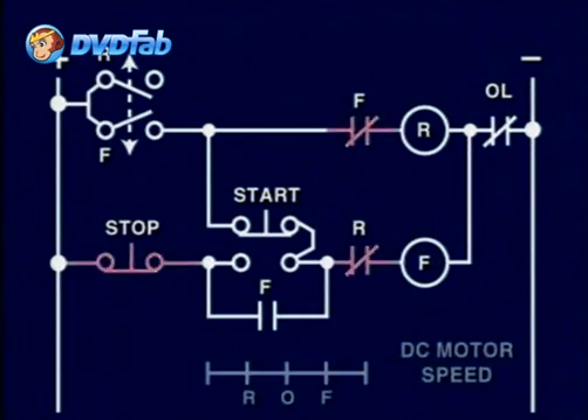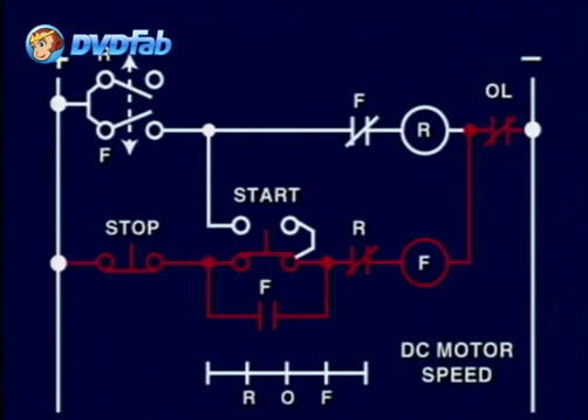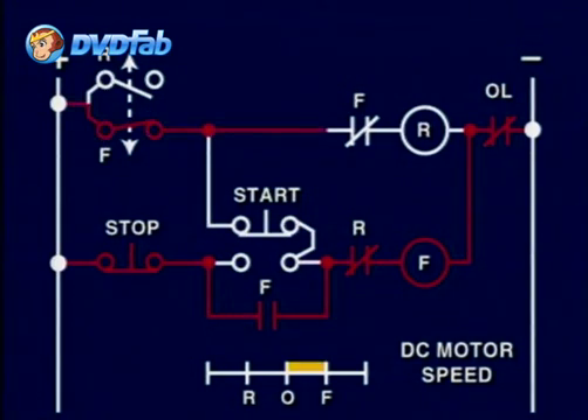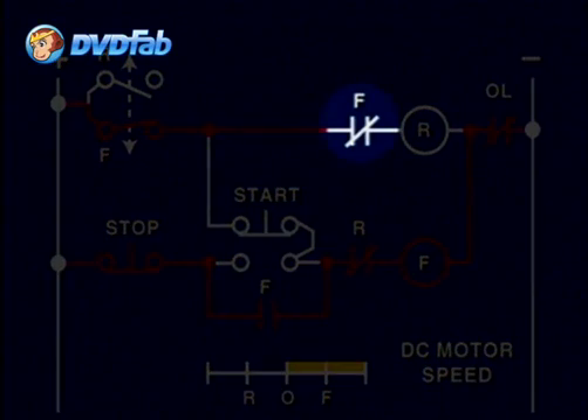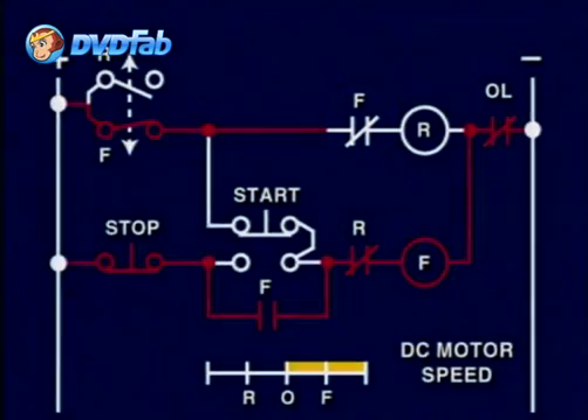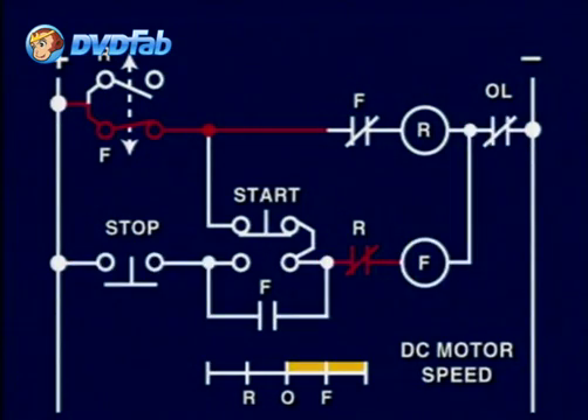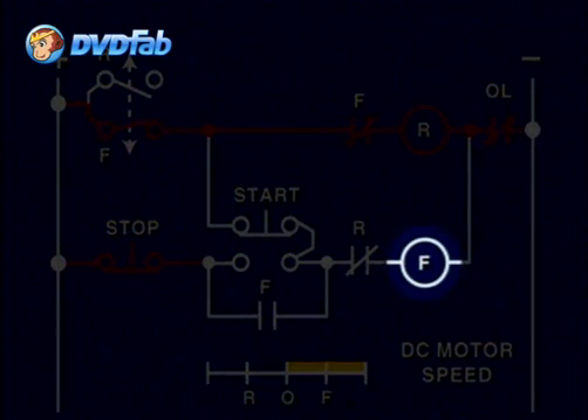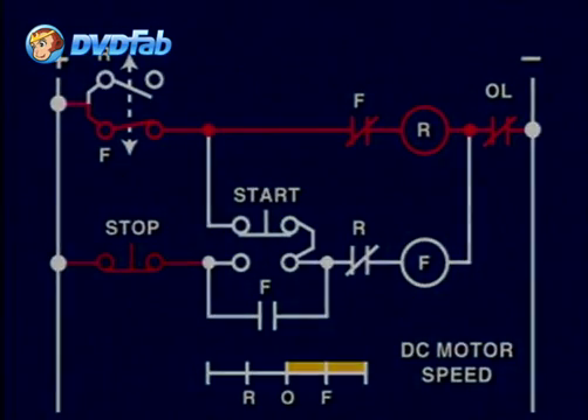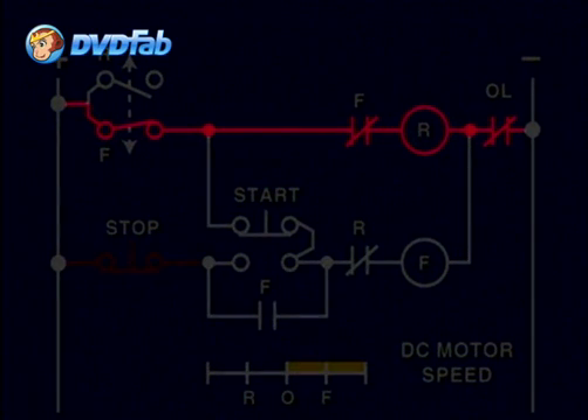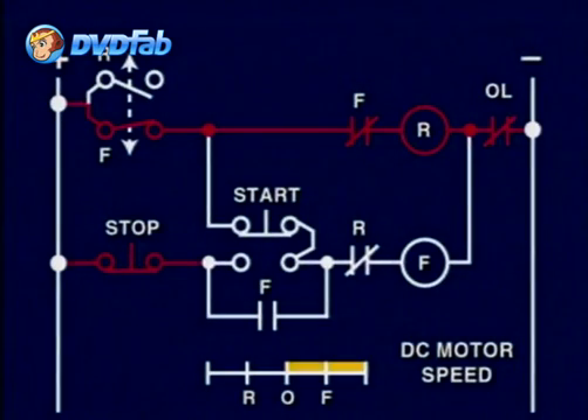Let's see. When start is pushed, the motor will start in the forward direction, and the plugging switch's forward contacts will close and set up the reverse motor to wait for the normally closed forward interlock to be back to its normal state. This will occur as soon as we press the stop push button, which will reset the forward starter coil. At this time, the reverse starter will be energized because there is continuity provided by the plugging switch forward contact, which is still closed by the centrifugal force due to the rotation. The reverse starter will be disconnected as soon as the rotation in the plugging switch slows down close to zero speed.